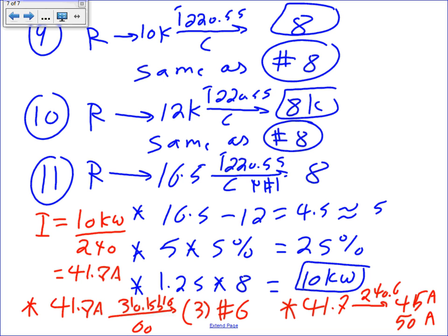Isn't the panel well over 100 amps? You can have a panel for 600 amps. Well, if it is, then you were supposed to use the 75 degree column. Yeah, but we're doing branch circuits, remember. Up to this point, we're sizing branch circuits. So it's just the individual breaker. Yes, individual breaker. You're right about the service, but the individual breakers are 75.